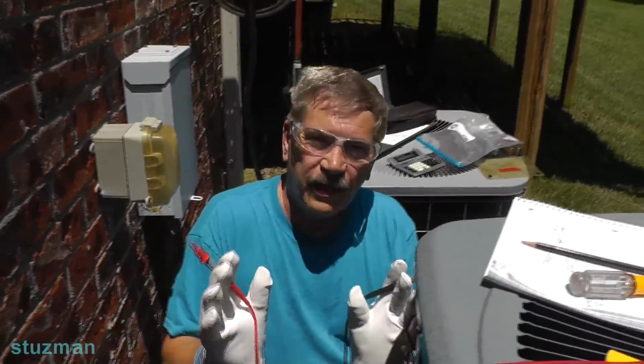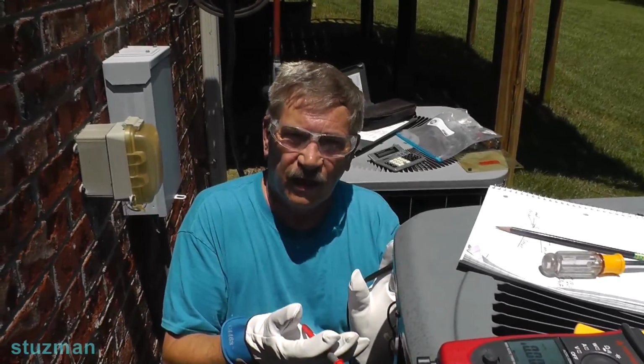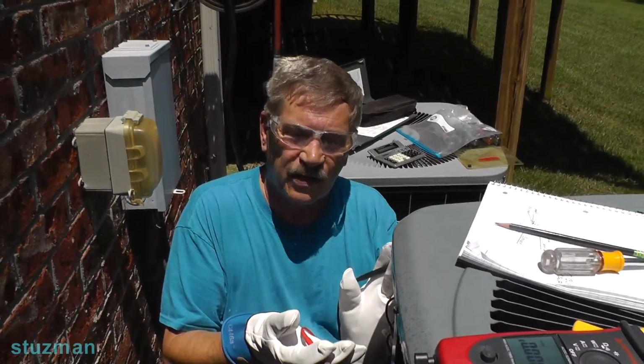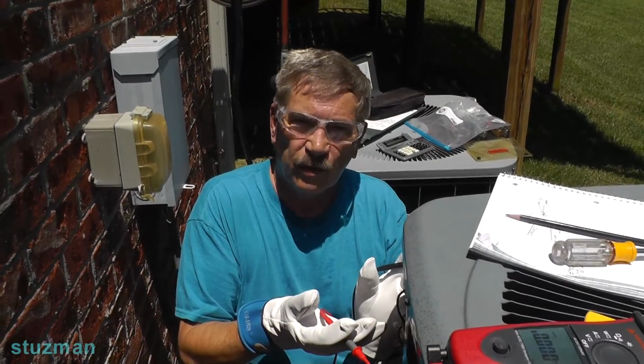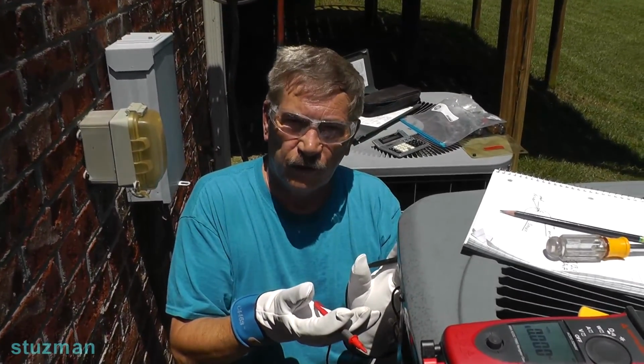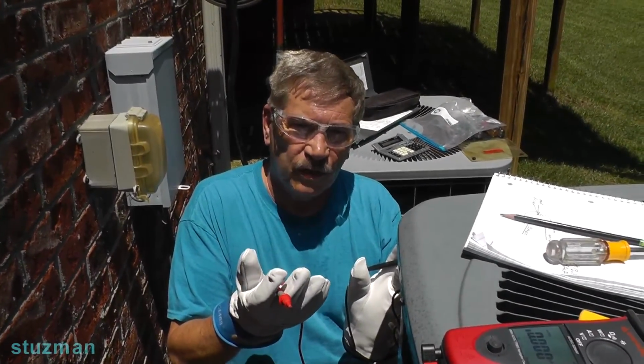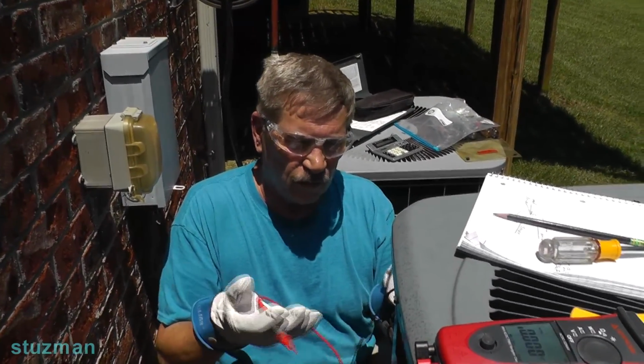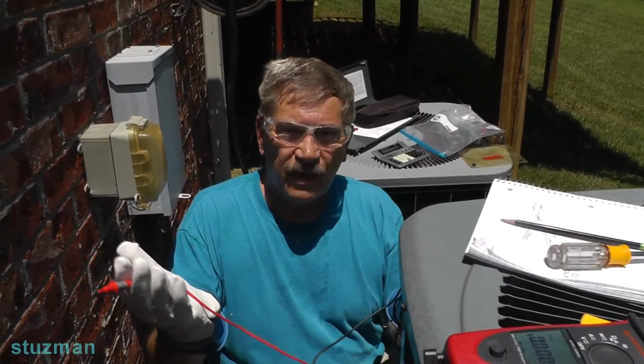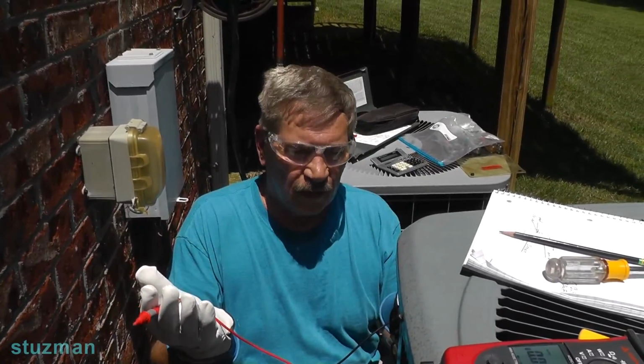So we're still within spec, but only by one microfarad. So at this point, it might be a good idea for me to go ahead and change this capacitor because this value is getting a little bit low on the one for the compressor. Now, as far as the other one, for 5 microfarad, that was 4.93 plus or minus 6%. So we're within spec on that.